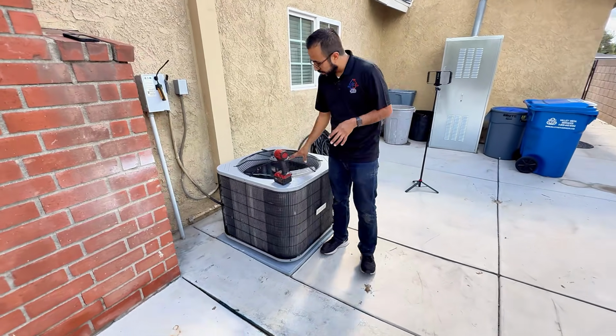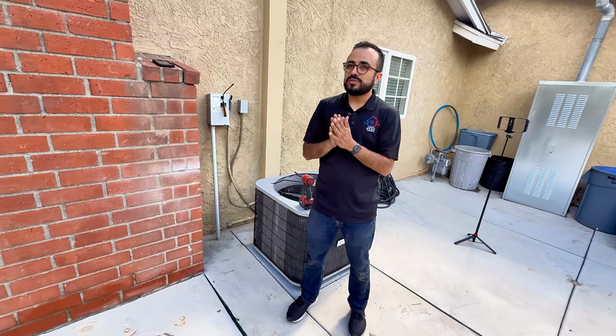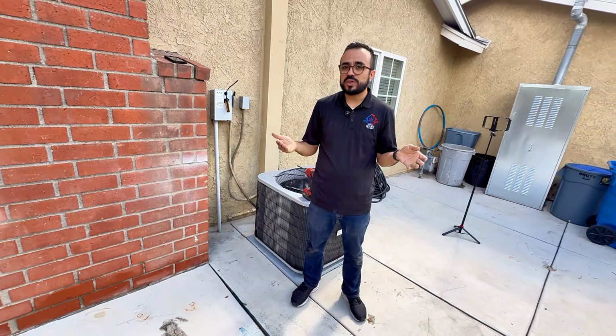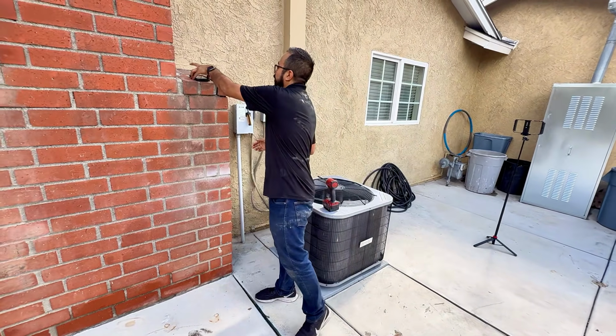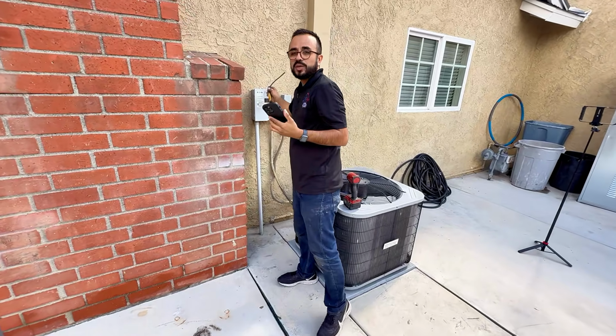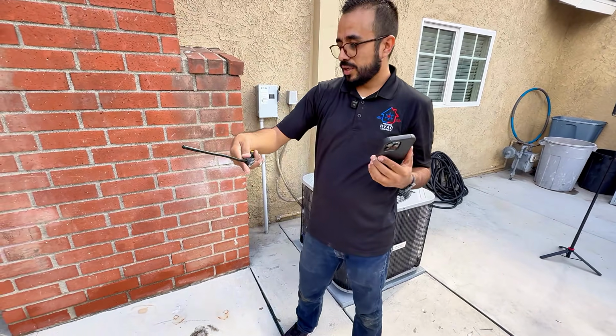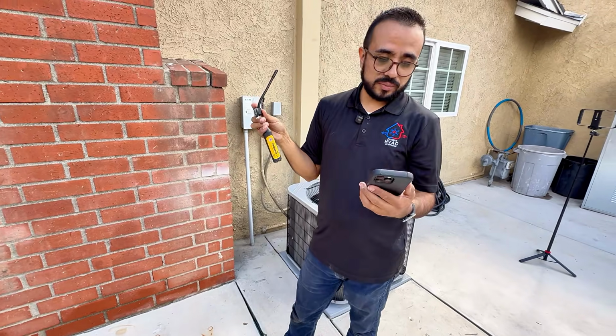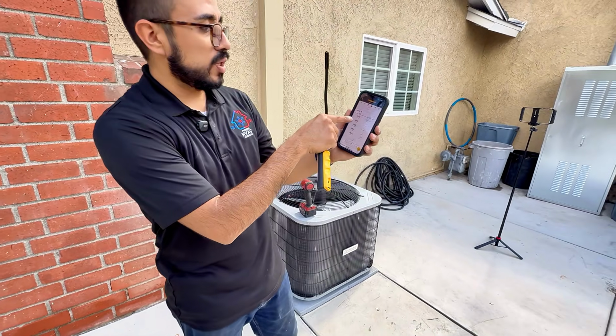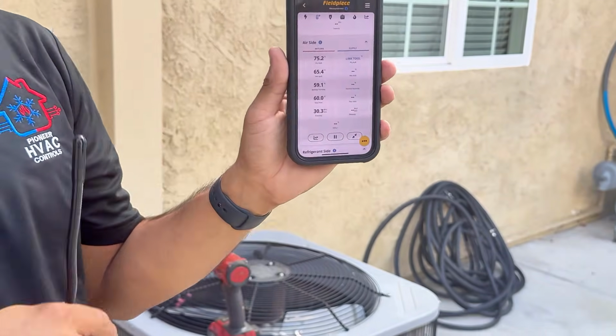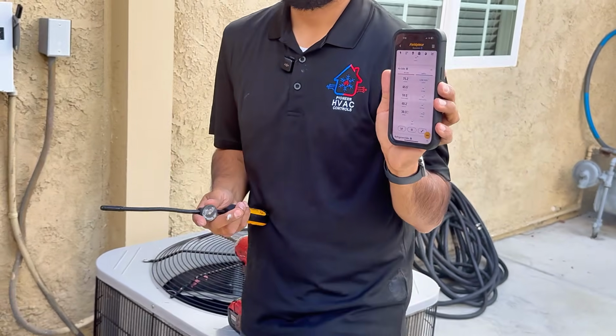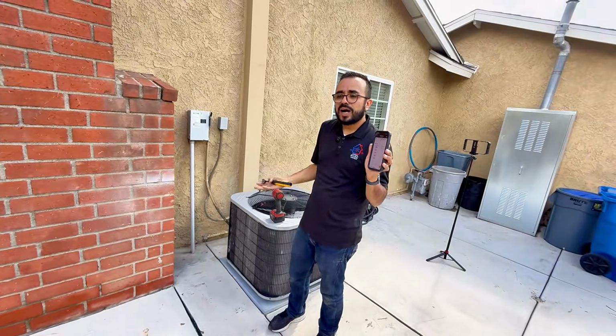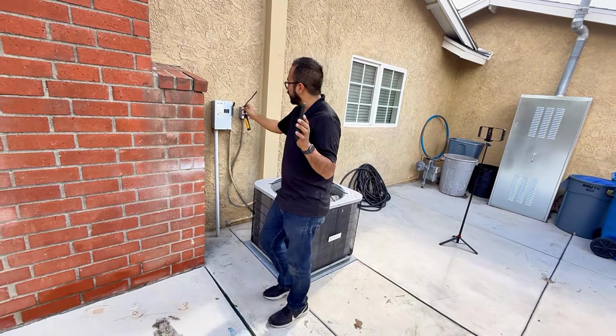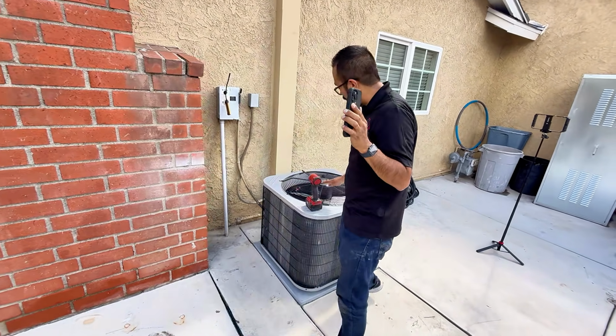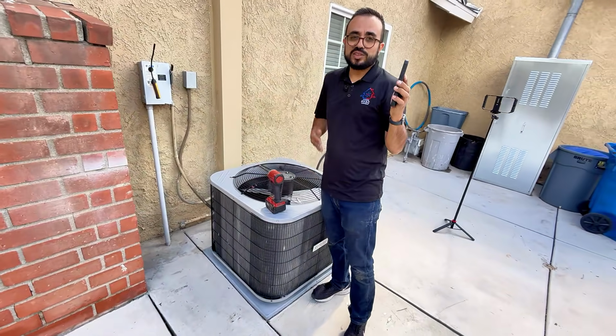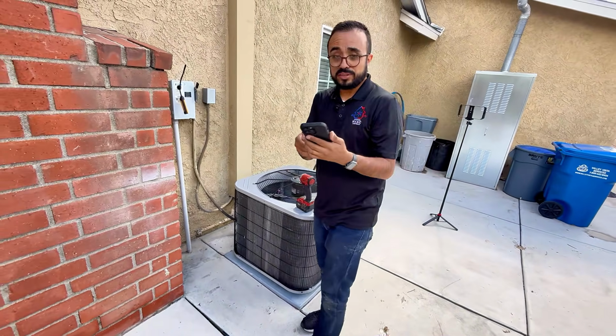For the cooling aspect, it has to be at least above, certain manufacturers will say above 70 degrees. Right now, fortunately, I had a buddy of mine who gifted me this Fieldpiece psychrometer. It reads all your temperatures, and right now we're reading 75 degrees, so we're in the clear. I would have liked it to be a little higher in temperature, but even if that's not the case, you could cover a little bit of the condenser fan to generate a higher head pressure, because that's important.